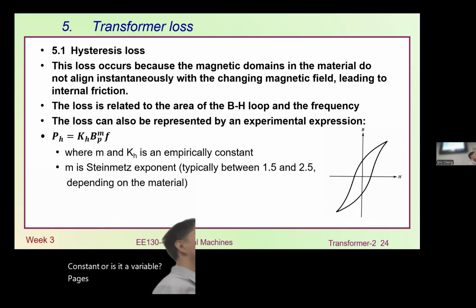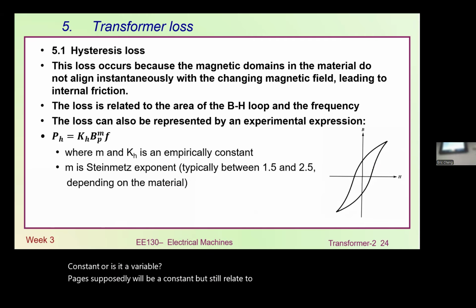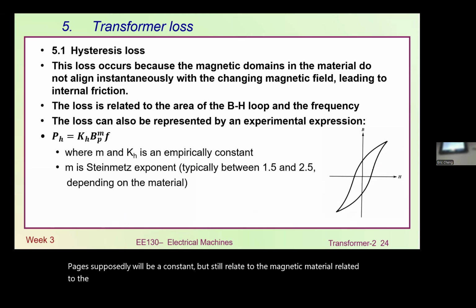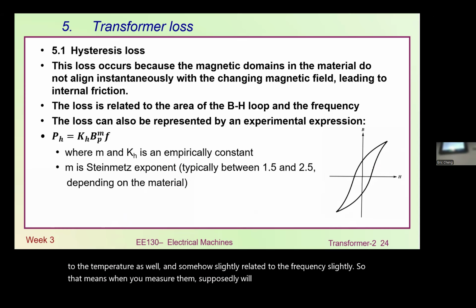Is K sub H a constant or a variable? K is supposedly a constant, but it still relates to the magnetic material, relates to temperature as well, and somehow slightly relates to frequency. So when you measure it, it will vary with a lot of parameters. But for the data typically provided, we call it a constant. So K is just the constant that balances out the formula.